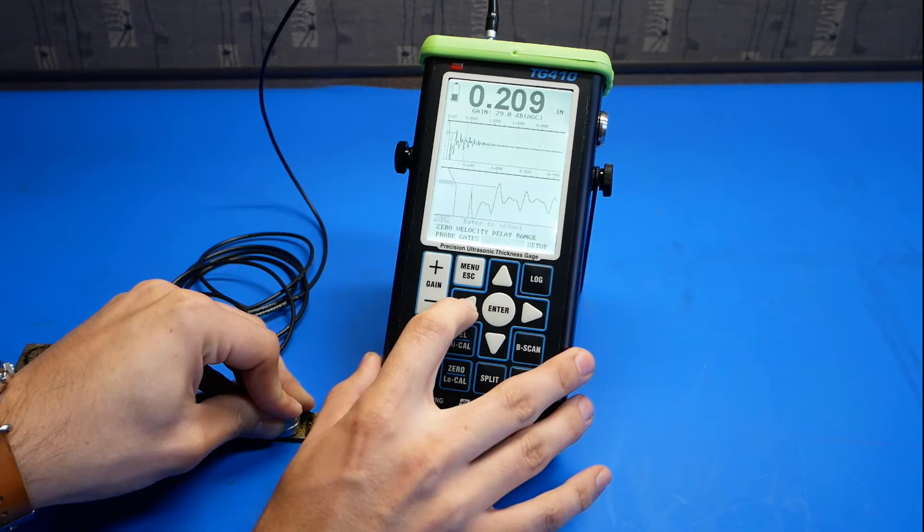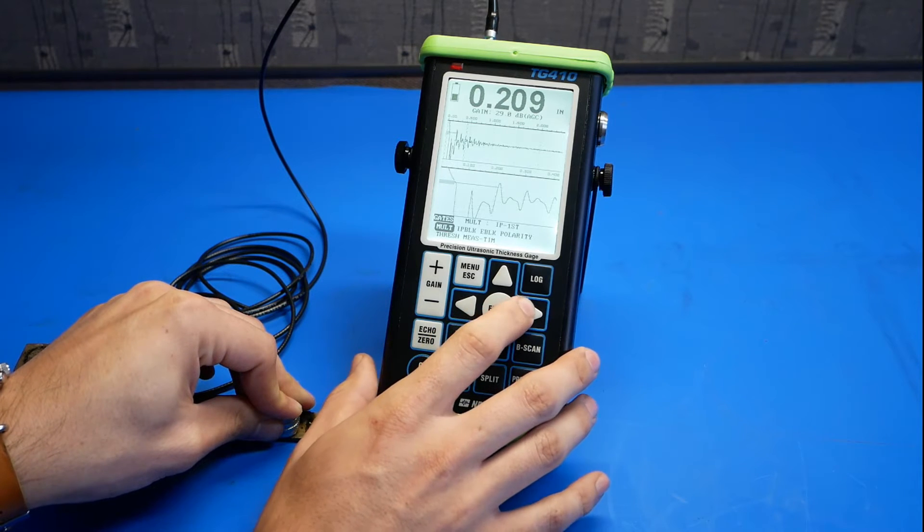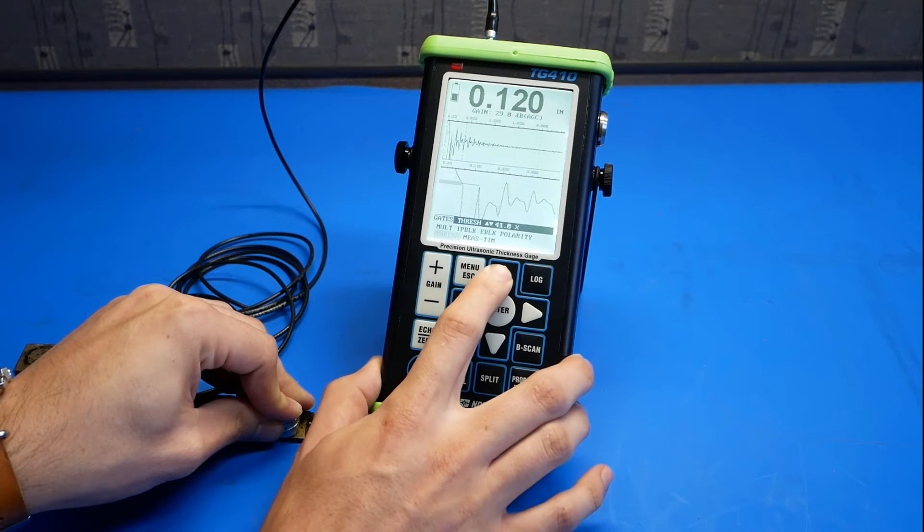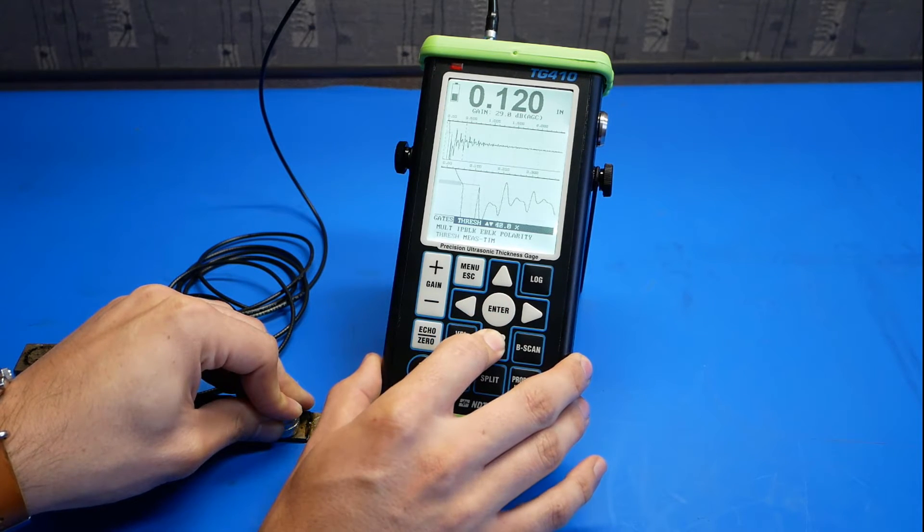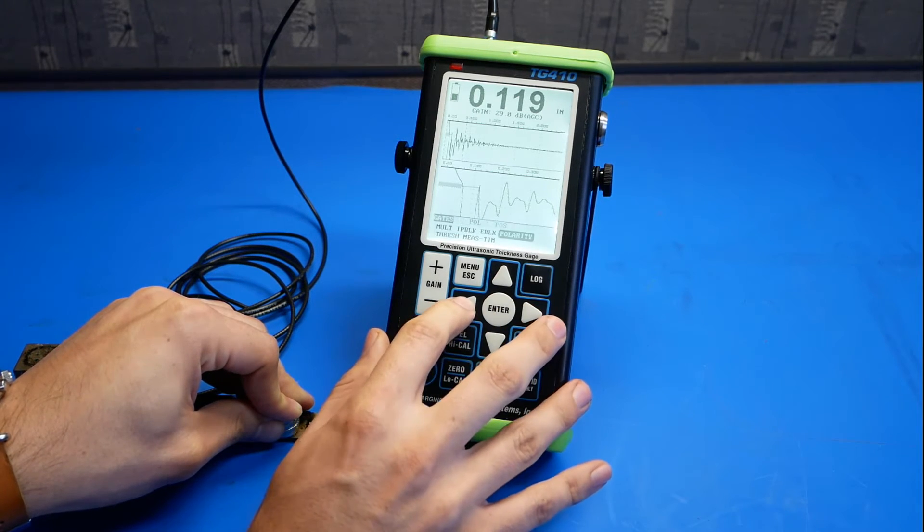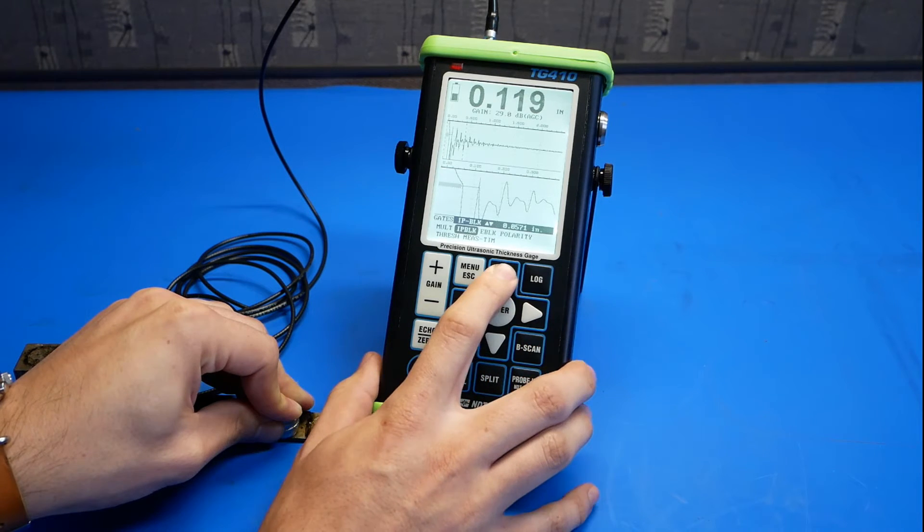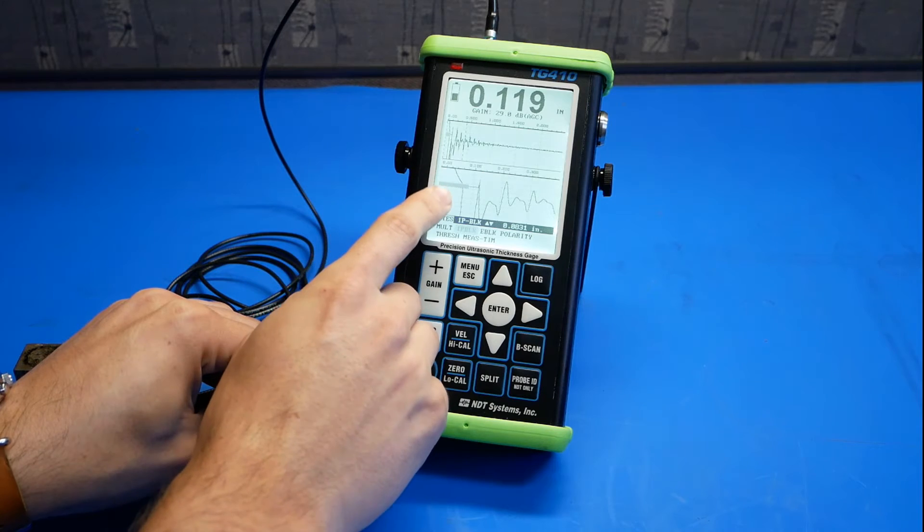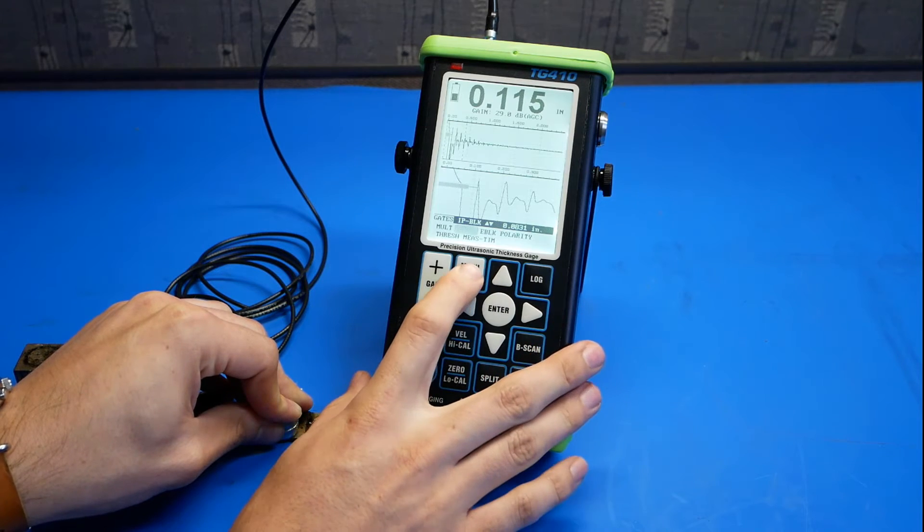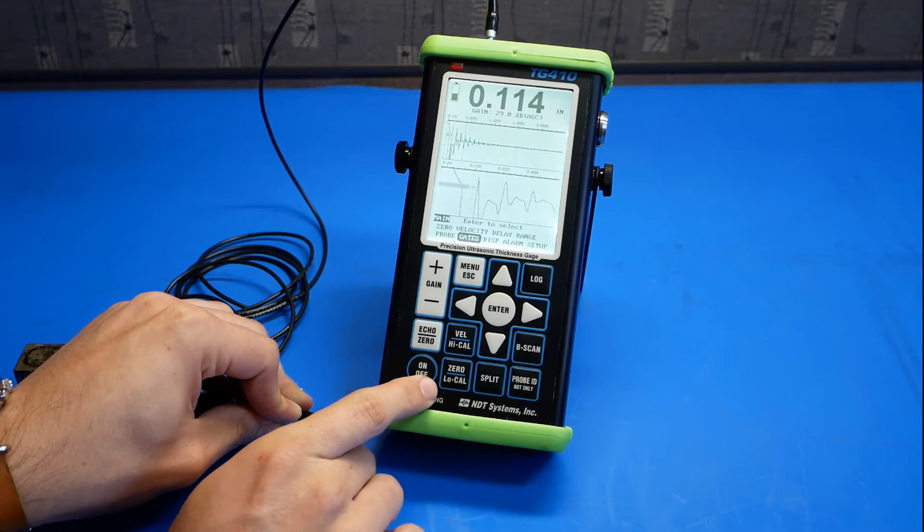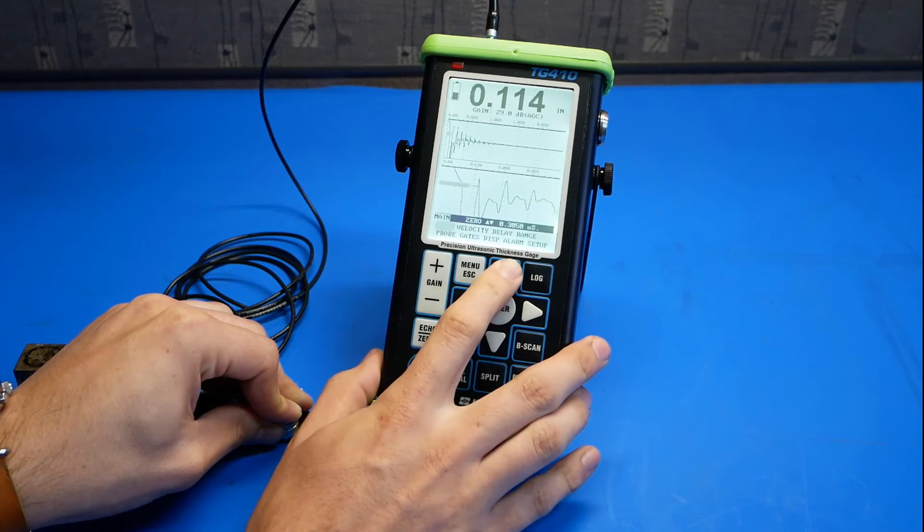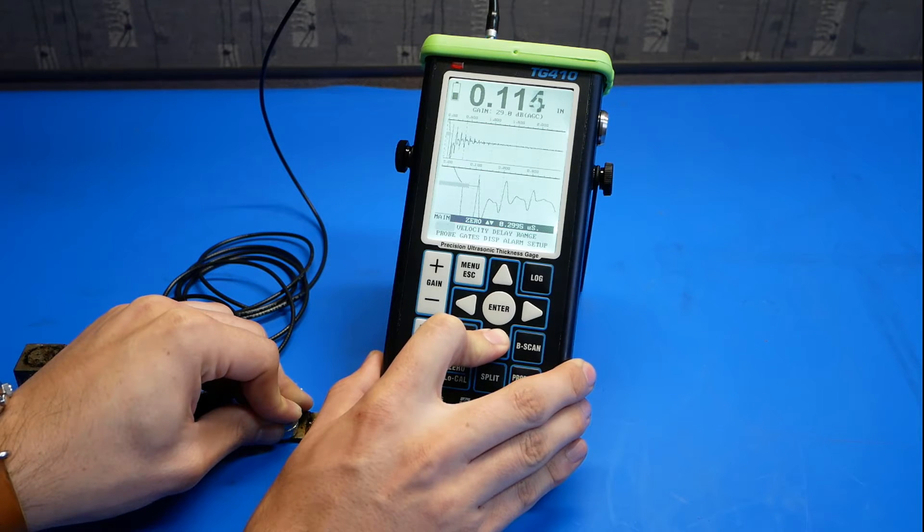We'll go to gates. We'll go to threshold, decrease that to 35 or 30%. Go to I.P. blank and pull that out so that the gate passes over the initial pulse here. Next, go to your zero low cal to calibrate the low thickness. Adjust the zero so that our reading measures 0.1 inch.